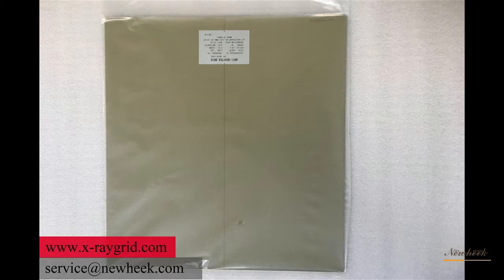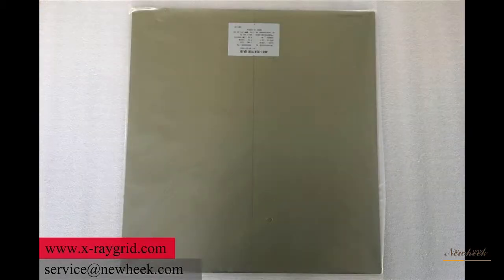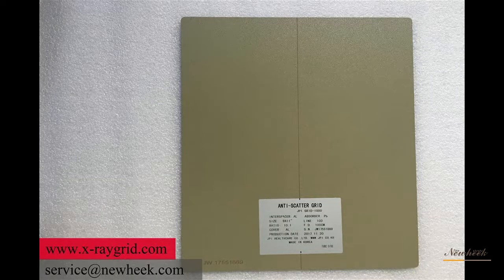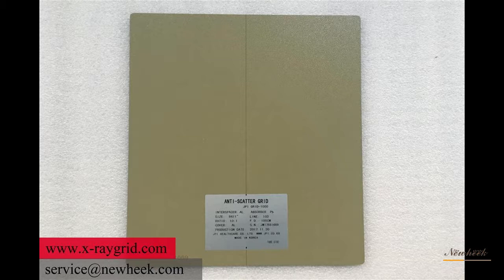The transmission of primary radiation is greatest because the absorption bars project the least amount onto the image receiving area. Any deviation of the focus from the virtual line at the convergence distance will increase the projection of the absorption bars onto the image receiving region, decreasing primary radiation transmission.